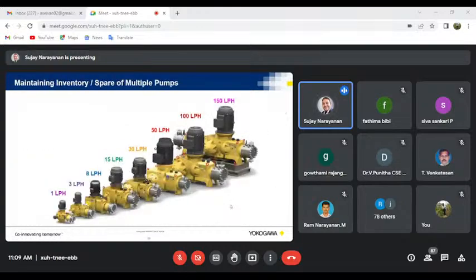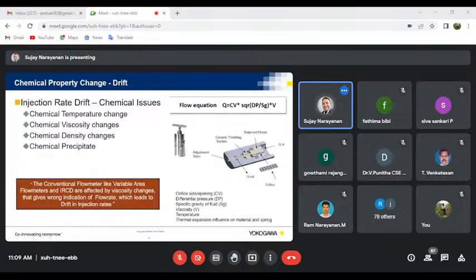The problem with these small control valves is, even if you use a control valve, this is the flow equation of the control valve. Q, the volumetric flow, equals Cv of the control valve times the square root of differential pressure divided by specific gravity, that's nothing but the density of the chemical, and the viscosity of the chemical is involved in it. So if there is any change in the specific gravity and the viscosity of the chemical, the performance of the control valve is affected. That's what I wanted to show over here.